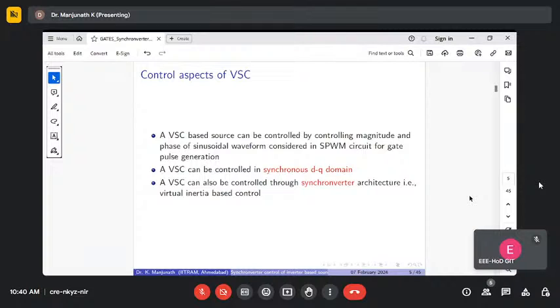Another way is to control the VSC using synchronous DQ quantities. In the modeling of a synchronous machine, there is a direct axis and a quadrature axis. By performing Park's transformation, ABC quantities are converted into DQ quantities. The advantage here is that DQ quantities are constant, while ABC quantities are sinusoidal. Controlling a sinusoidal signal is more complex than controlling a constant quantity. Because of this nature of DQ signals, we use this advantage to control the VSC.